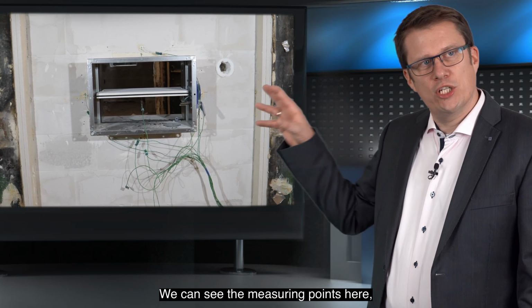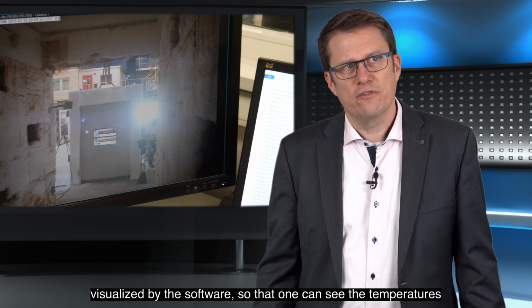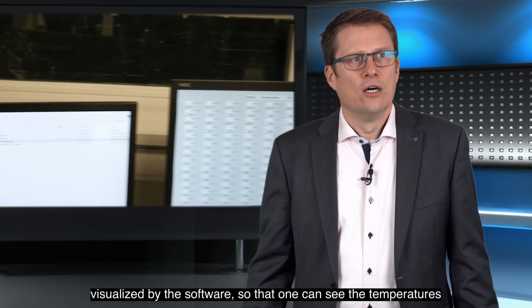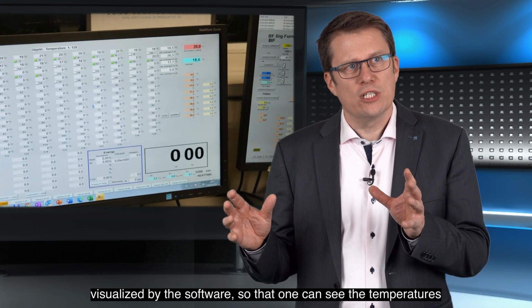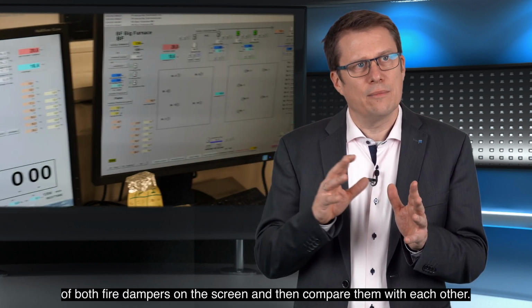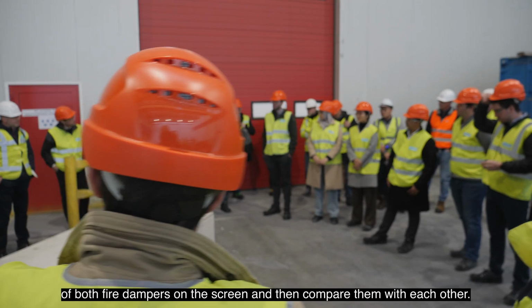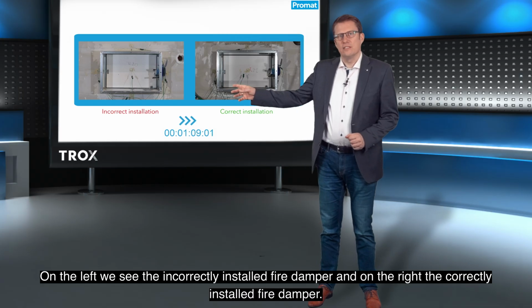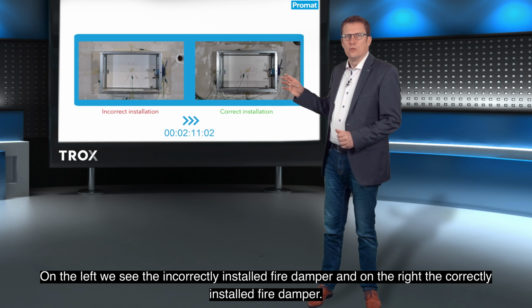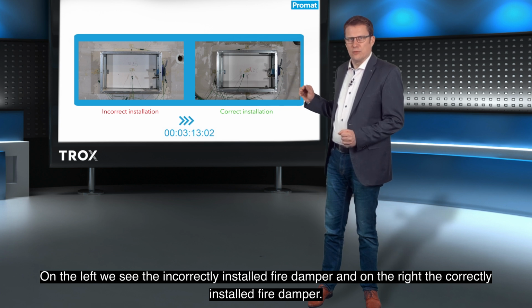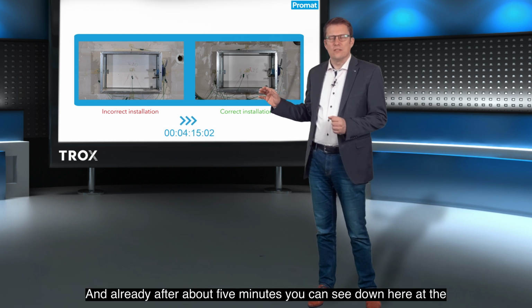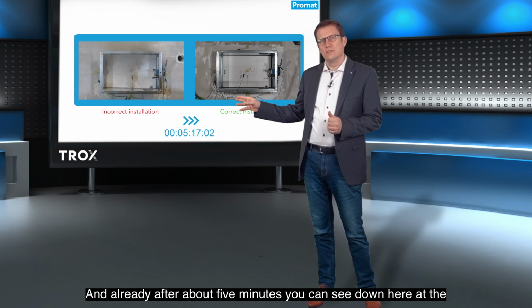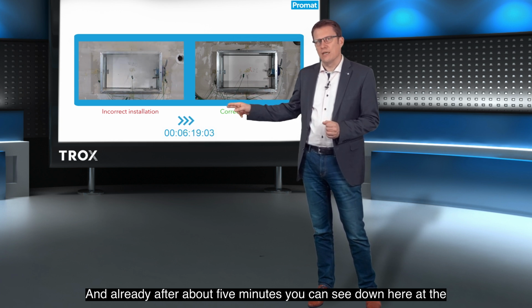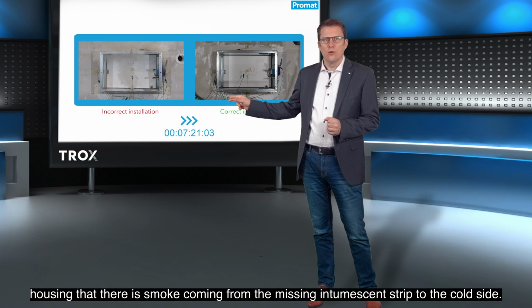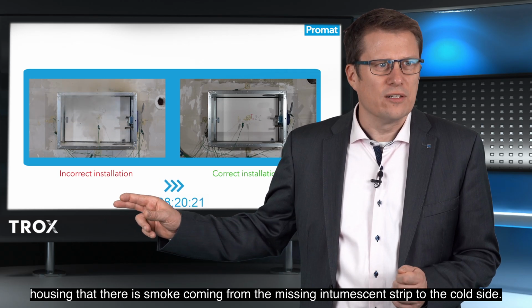We can see the measuring points here, visualized by the software, so that one can see the temperatures of both fire dampers on the screen and then compare them with each other. On the left, we see the incorrectly installed fire damper, and on the right, the correctly installed fire damper. And already after about 5 minutes, you can see down here at the housing that there is smoke coming from the missing intumescent strip to the cold side.